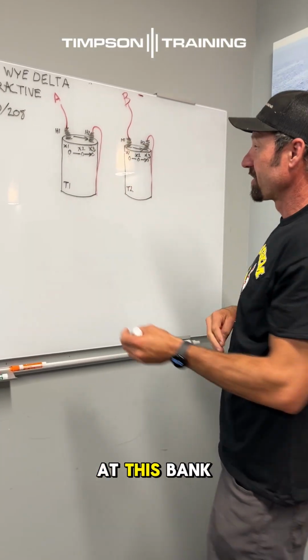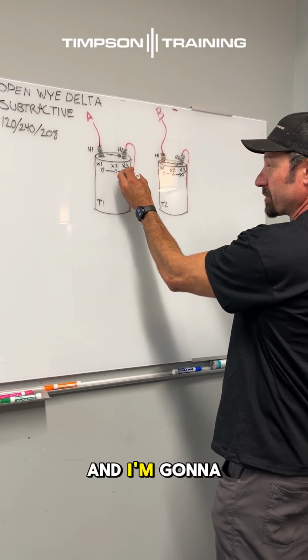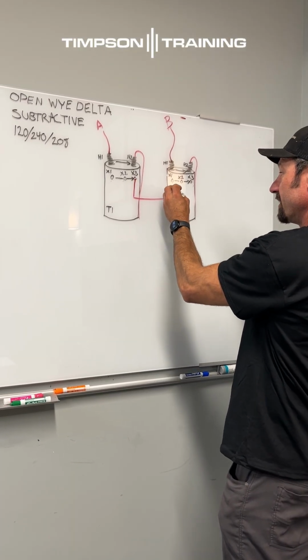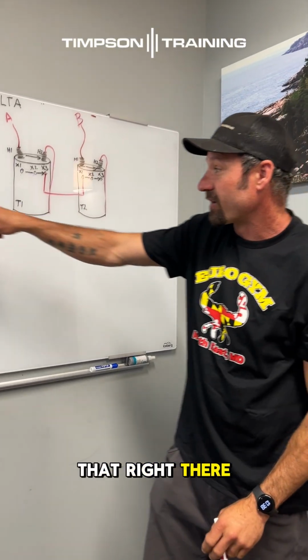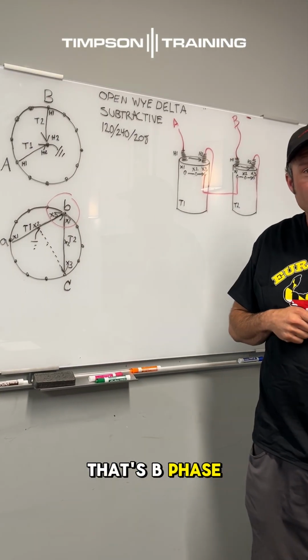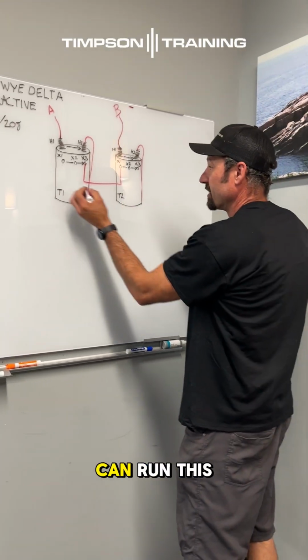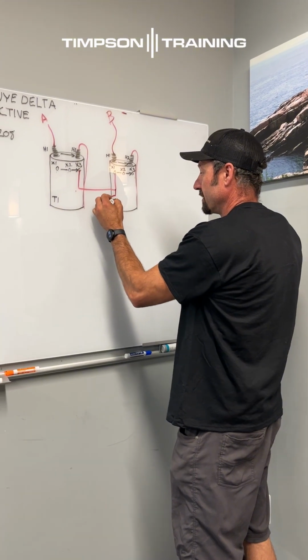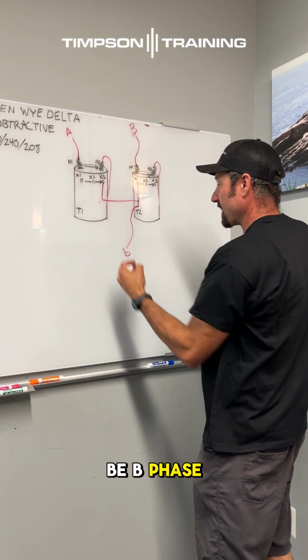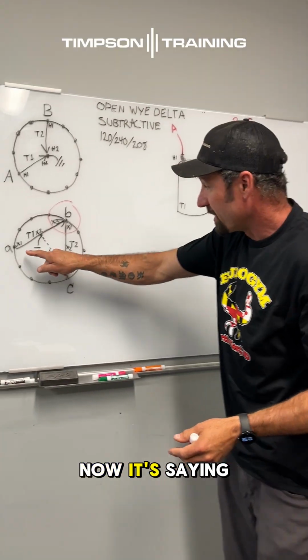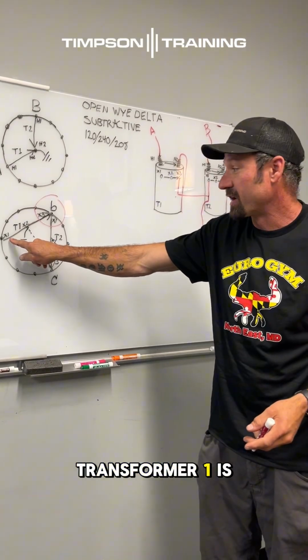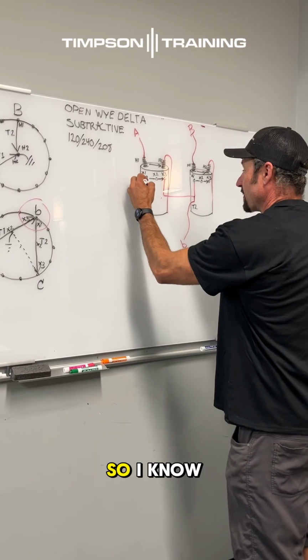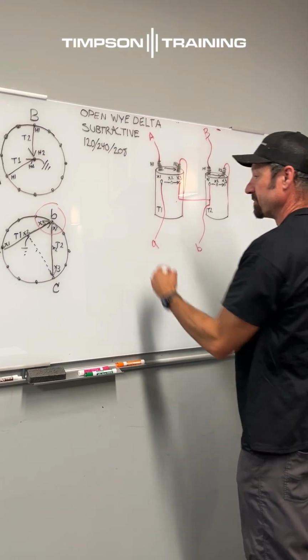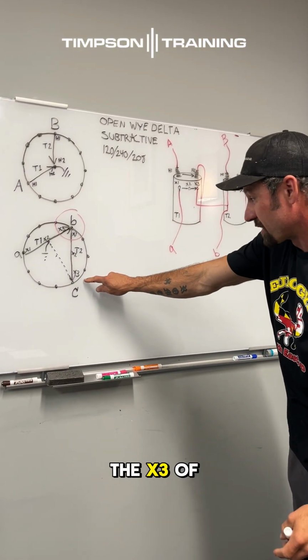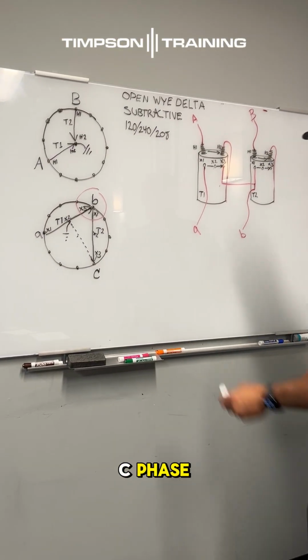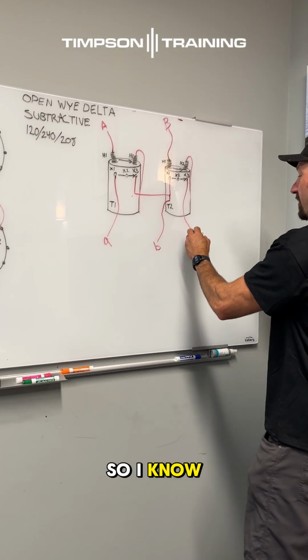So I know if I'm looking at this bank, in order to do that, I'm going to take a tail and I'm going to install that right there. And that's telling me that's B phase. So I already know that I can run this down and this will be B phase. Now it's saying the X1 of transformer 1 is A phase. So I know that this is going to be A phase. And it says the X3 of transformer 2 is C phase. So I know that's going to be C phase.